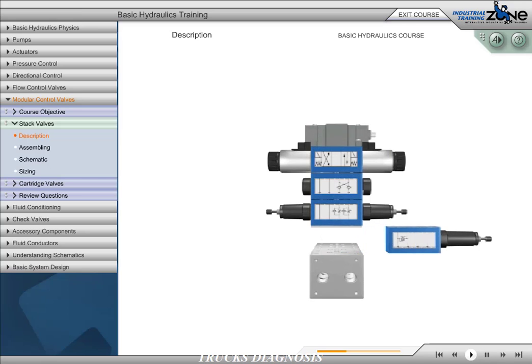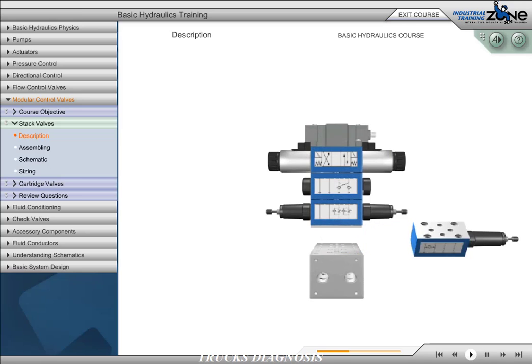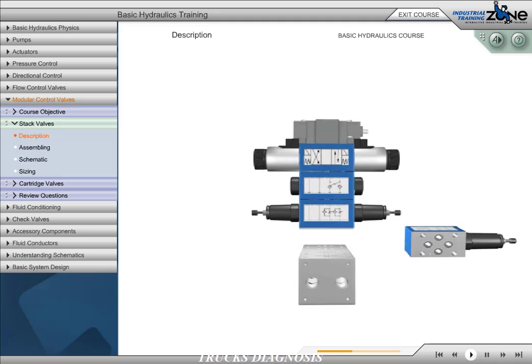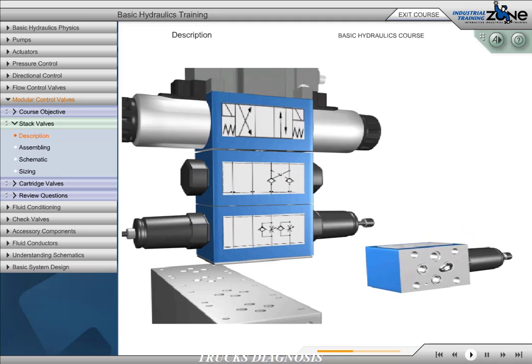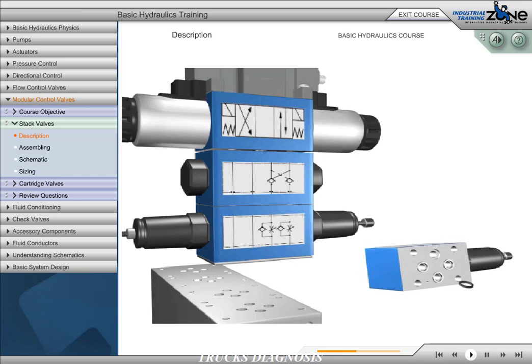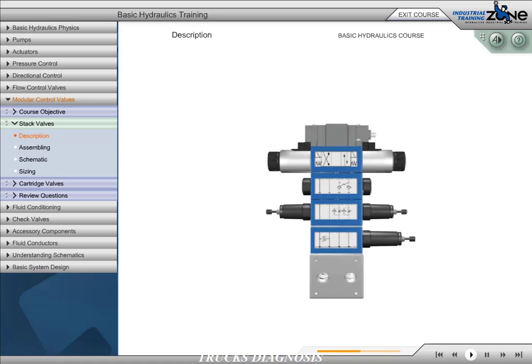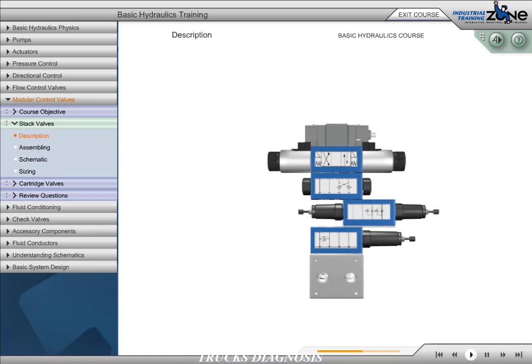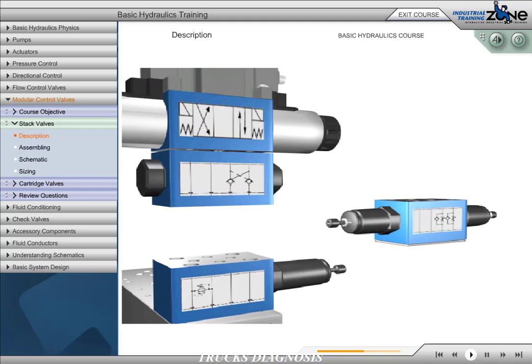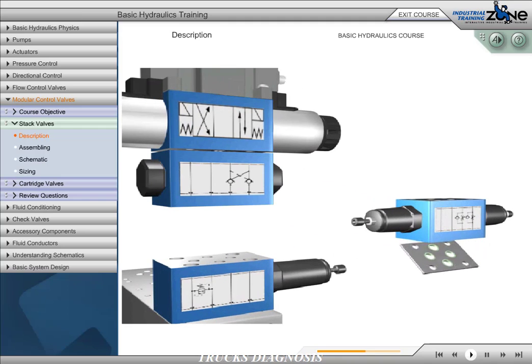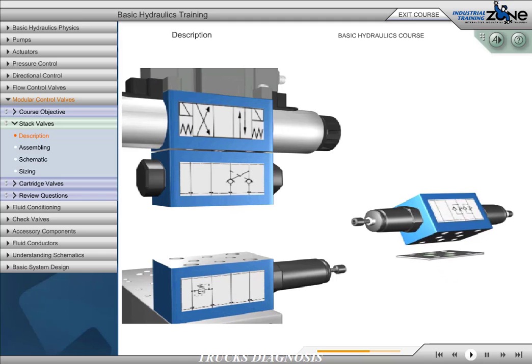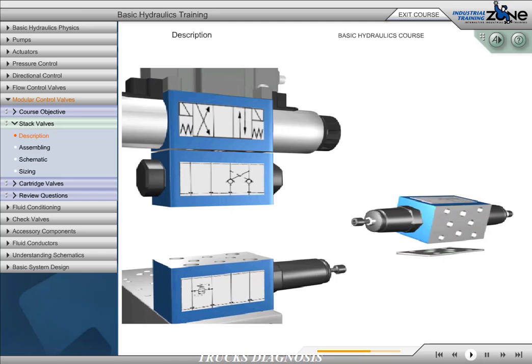Each valve block has a mounting surface on the top and the bottom. Valve blocks that can only be mounted in one position have a chamfered O-ring seat around each port on the bottom mounting surface. Flow control valves can be rotated to change the metering direction of the valve. A thin sealing plate holds the O-rings in place, creating the sealing surface for the flow control valve.